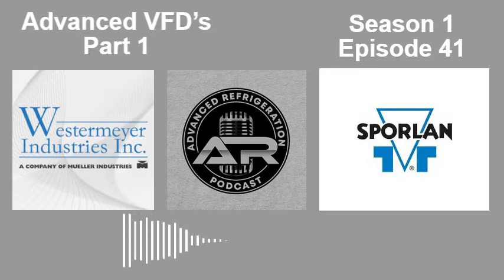So what U.S. Motors did, kind of on the side, they saw that there was a huge market for HVAC motors for these applications. And so they took our designs and made what's called the Very Tough motors. The Very Tough motors come with or without the shaft grounding rings, and those motors are extremely durable. They're inverter duty. They pass all the NEMA qualifications for inverter duty motors. You can get them without shaft grounding rings or with shaft grounding rings, and we call that an A motor. And we call our motor an A plus motor because it's got a few more features in it that they didn't put in the Very Tough motor line.